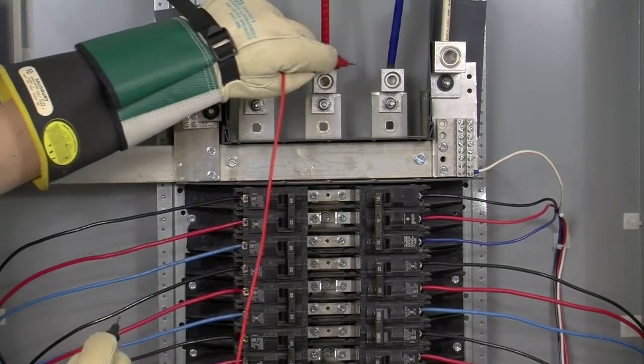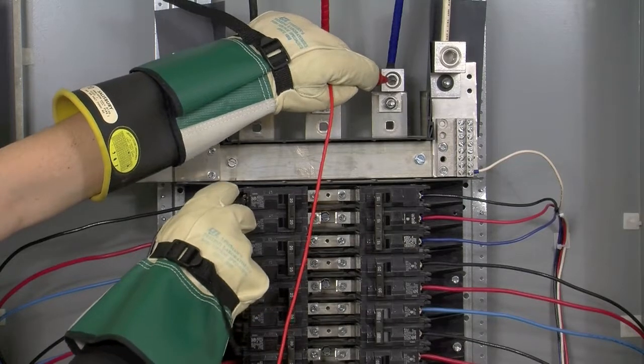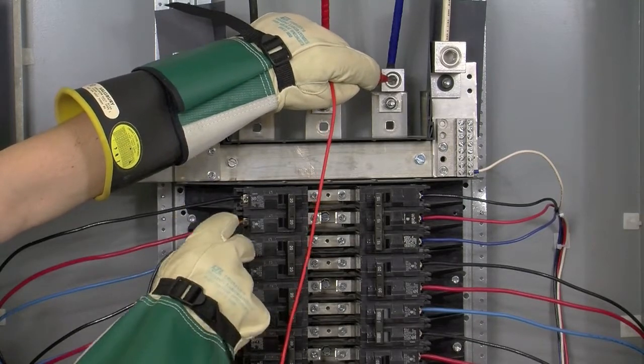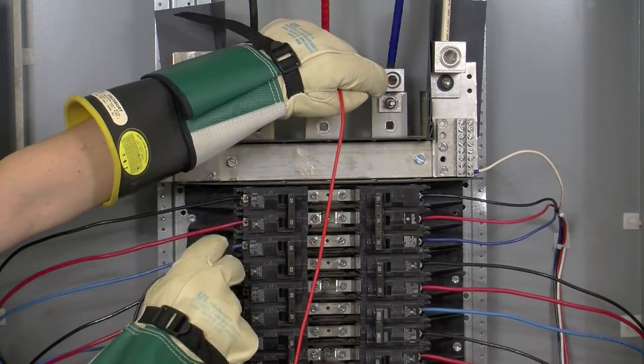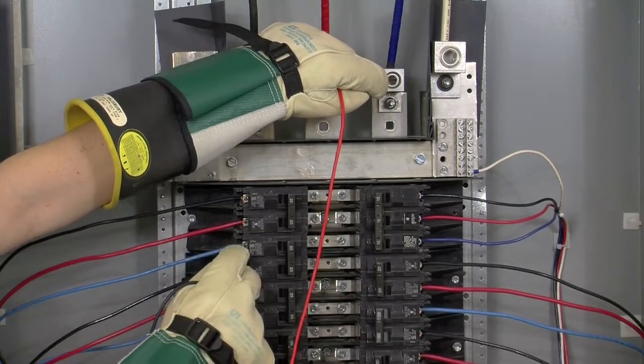Moving on to phase C. Here we have 208 volts difference. Here we have 208 volts difference. And here we have 0 volts difference. So we know that the third pole down is phase C. We're going to want to repeat this phase test for every line that we have CTs installed on. Once all the phasing is identified, we can go ahead and install our CTs.